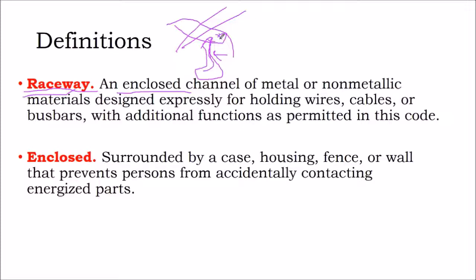If you have DC conductors coming off the back of the module and they're inside the home, they must be in a metal raceway. But if they're not in that metal raceway, then how do we enclose them in a metal raceway? You might get a nitpicky inspector that would fail you unless you identify that, hey, we're going into the metal raceway as soon as we can in this system, but that might mean there might be a half an inch of space. And so you want to point this stuff out during the design process to the AHJ so that you can do fancy building integrated solar projects.